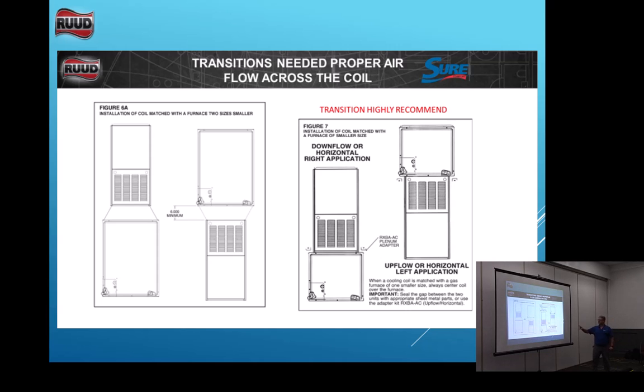I've had a few instances where he has put this in a closet and he's put it all to one side and he's got 4 inches on one side. Mike, I can't get my temperatures right. My pressures are doing this. You got it centered in there? No. I said, well, didn't we do that on the last one? Didn't it fix it? Yeah. Okay, why don't you put it centered again and call me back? And he called me back a week later. Hey, Mike, it fixed it again? Well, that's why it says it needs to be centered on that evaporator coil. But this is kind of easy to do in a closet, right?